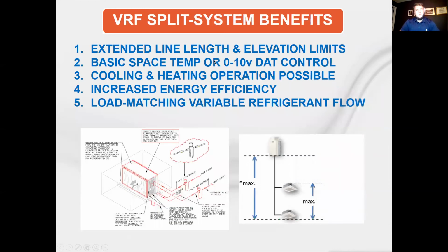To discuss some of the benefits of moving to a VRF type of split system instead of the traditional, many times we've even been forced into the VRF system strictly on the extended line length and elevation limitations, where traditional systems might be limited by 50 feet of elevation and a total of 150 feet split max. Some of the new VRF systems can go up to 350 total feet in high rises in the downtown Chicago market and all that. It can be quite beneficial for these types of systems to be paired with just a regular air handler.